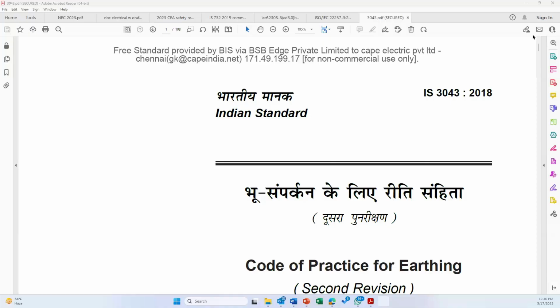ISI design is given. I got a book also, though I'm not remembering the number immediately. ISI has very well given the earth pit design. As a consultant, I insist that you must have an earth pit of this design, but in most places earth pits are not designed as per ISI. So this is contradictory, because once you have achieved the equipotential, an earth pit is not required. If you say equipotential is achieved, afterwards a potential difference may still be established. Equipotential is not a constant parameter. It will definitely change depending upon the load. That's what I feel.